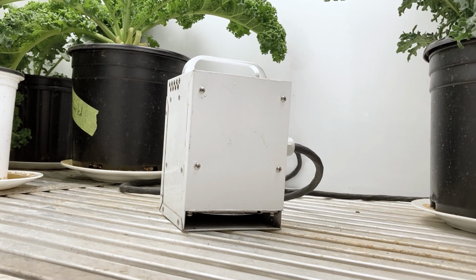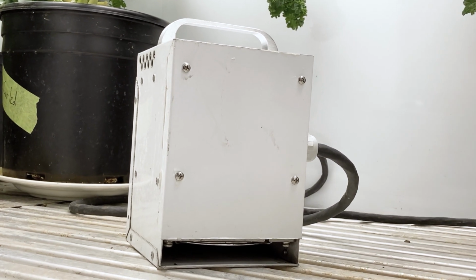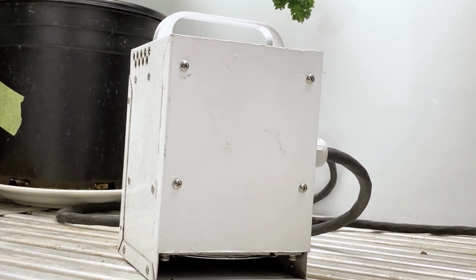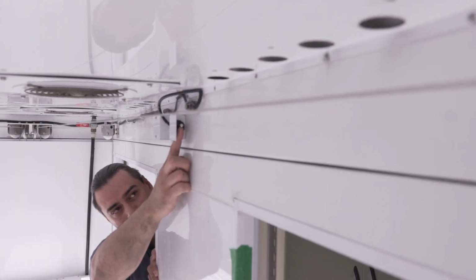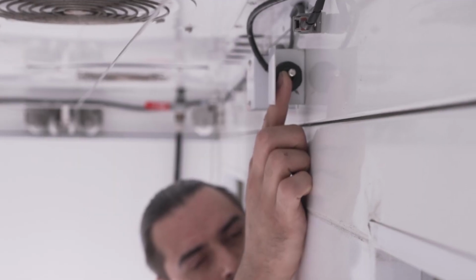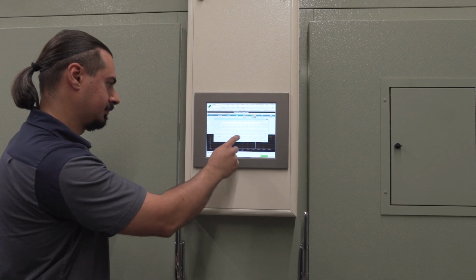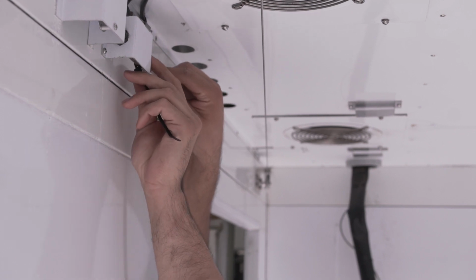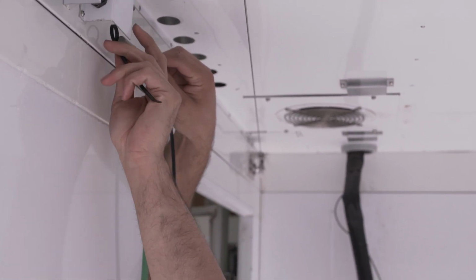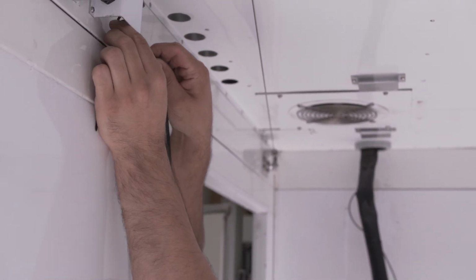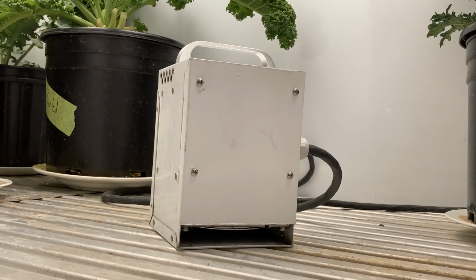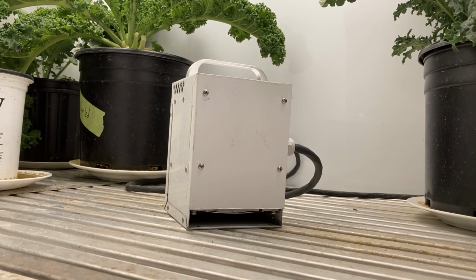All chambers have 3 independent temperature sensors, one for chamber air temperature, one for high-low limit temperatures, and one for safety. When the lights are off, all 3 temperature sensors should read close to the same. First, insert a recently calibrated thermistor temperature sensor next to the chamber temperature set point and limit sensors inside the white aspirated sensor box in your growth chamber.